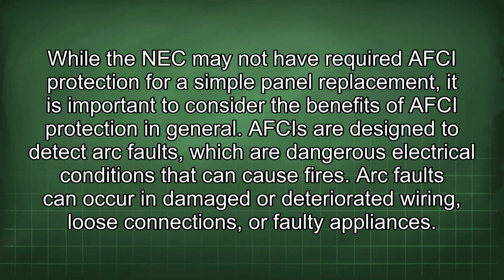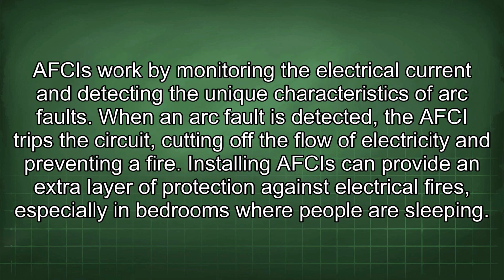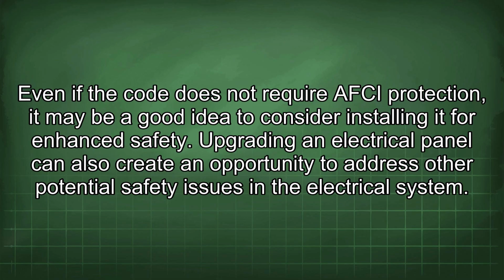AFCIs are designed to detect arc faults, which are dangerous electrical conditions that can cause fires. Arc faults can occur in damaged or deteriorated wiring, loose connections, or faulty appliances. AFCIs work by monitoring the electrical current and detecting the unique characteristics of arc faults. When an arc fault is detected, the AFCI trips the circuit, cutting off the flow of electricity and preventing a fire. Installing AFCIs can provide an extra layer of protection against electrical fires, especially in bedrooms where people are sleeping.